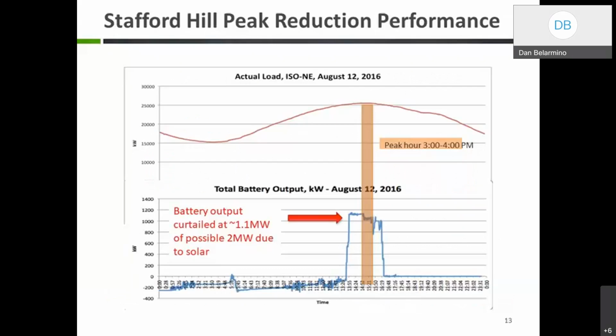This one shows the peak reduction performance of Stafford Hill in 2016, and how it got curtailed. As you remember, Stafford Hill is a 2 megawatt battery system output capacity, but during peak hours the battery output is curtailed to 1.1 megawatts instead of the possible 2 megawatts, due to solar.